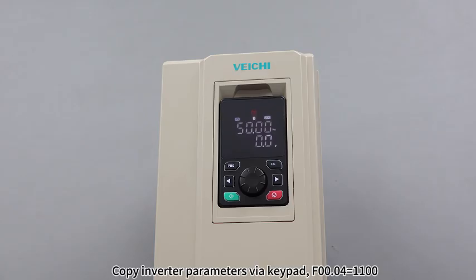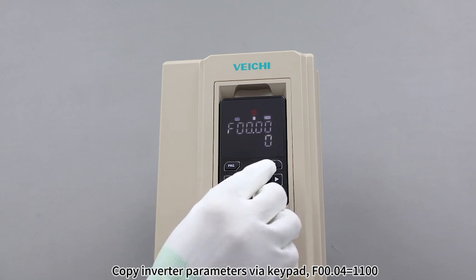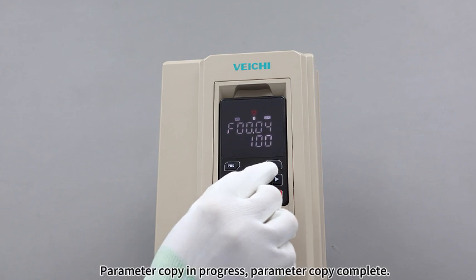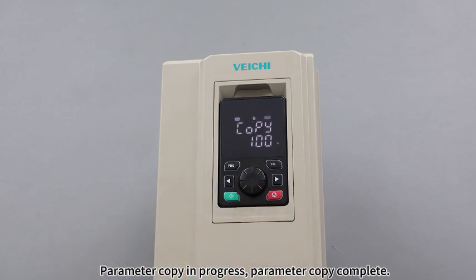Copy inverter parameters via keypad, F00.04 equals 1100. Parameter copy in progress. Parameter copy complete.